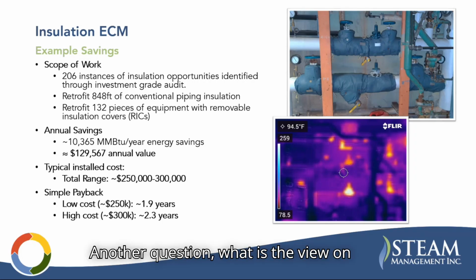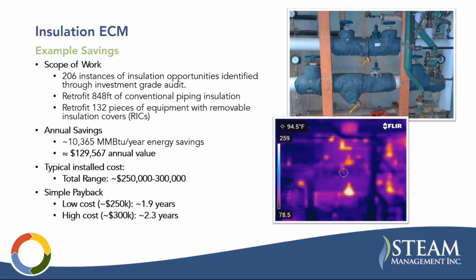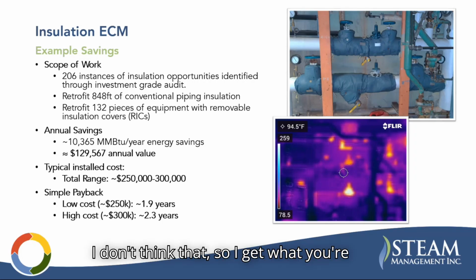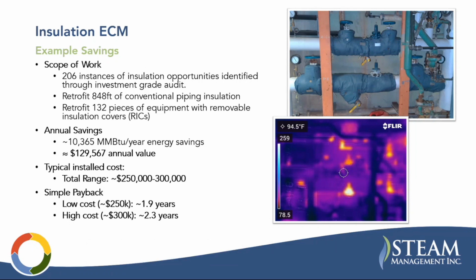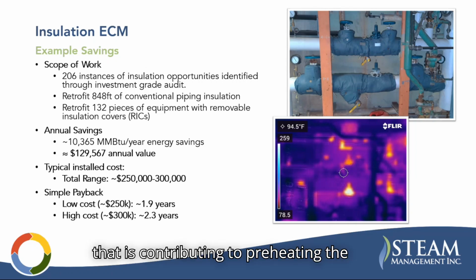Another question: what is the view on insulation on devices near the boiler? Preserve all heat in the line, or is it preheating the combustion air to the boiler? Oh, I don't think that. So I get what you're saying. If you were to lose heat from components in the boiler room, that is contributing to preheating the combustion air in the boiler.